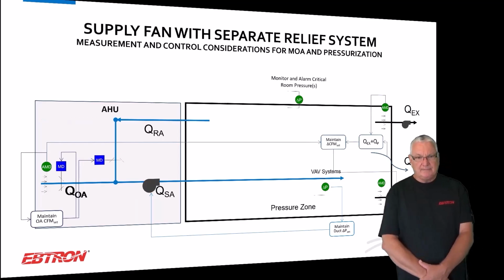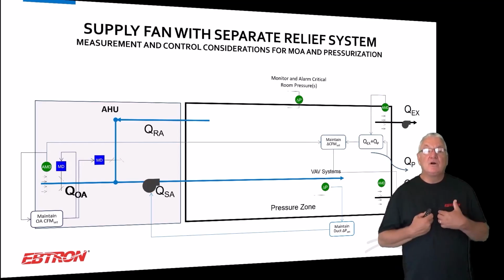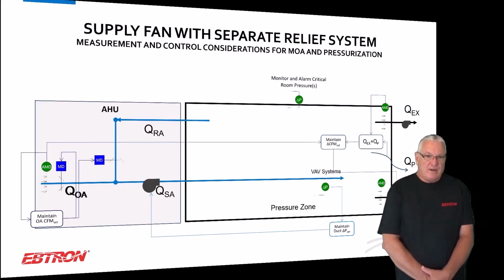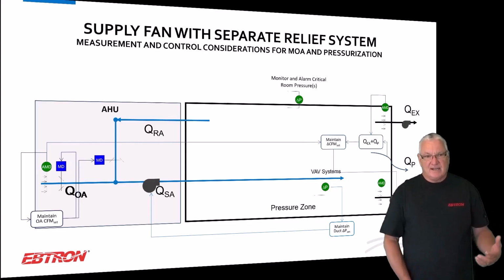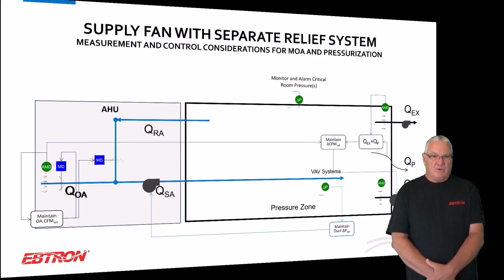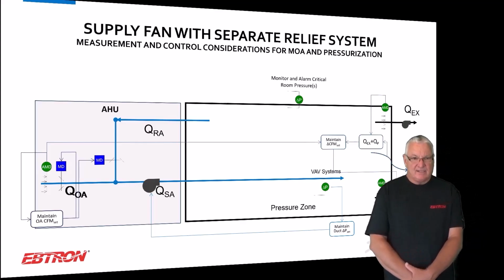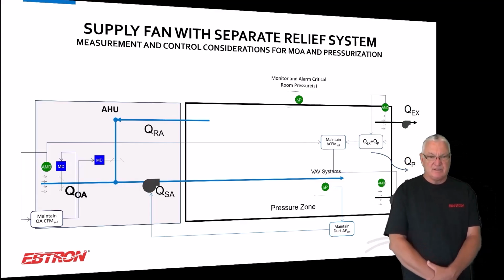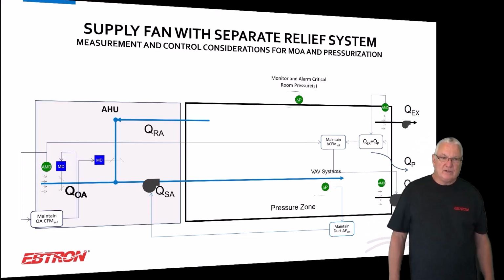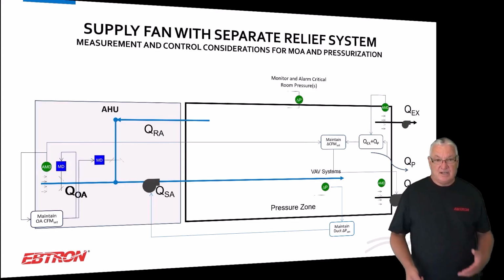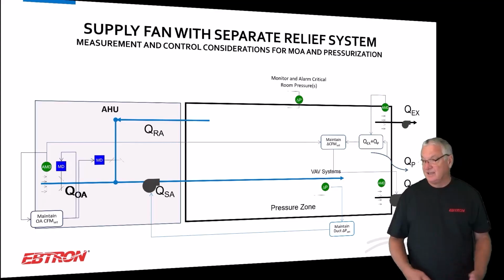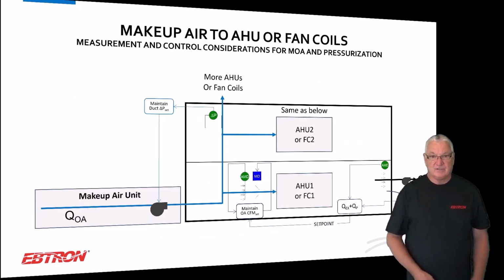When we get into cases where we don't have any relief, where we're exhausting at the air handler, if it's at the air handler, I always call it relief. But if we don't have any relief or exhaust at the air handler, then we have outside air and we have relief air. That's fine, but keep in mind that the accuracy can be somewhat compromised on some of these measurements. Outside air may not be accurate enough on some of your units to do good differential flow control. The relief air path may not be good enough. So you've got to pay more attention to where you're locating the flow measurement. Is it ducted? There are cases, not so much in healthcare, where the relief fans are just fans in the ceiling. I don't think you're going to get a good enough measurement to do this. But the bottom line is you're controlling these two differentials.